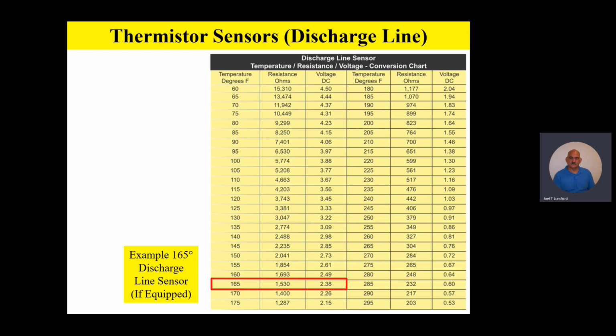But hang on a second, we can always do a sensor check with the sensor plugged back onto the board, as long as that board is reading 4 to 5 volt DC with nothing plugged on. If I plug that sensor back onto the board and I take my DC voltmeter and my needlepoint meter leads, in this example here at 165 degree discharge line temperature, and about 1500 ohms with it unplugged off the board, I plug it back onto the board. I should read about 2.38 volt DC with the sensor plugged back in. So team, that's how we do it. That's how we check sensors.